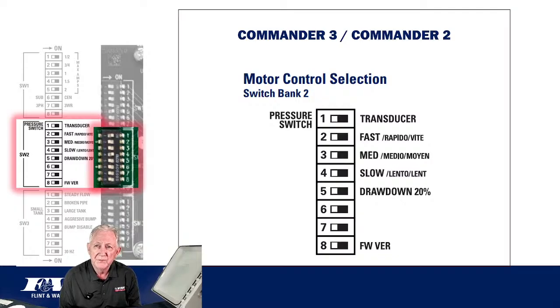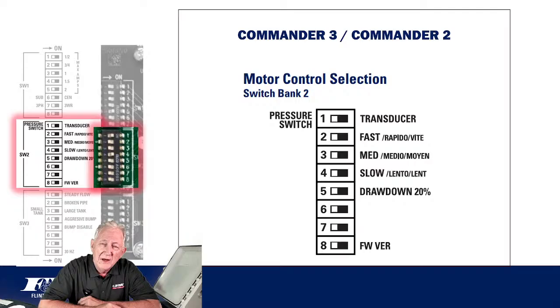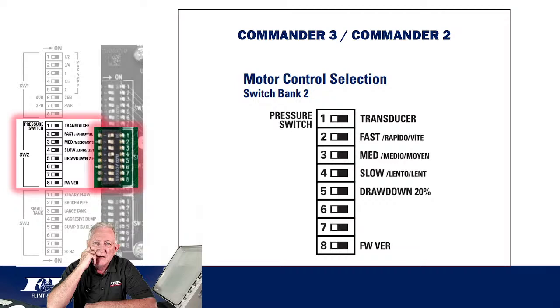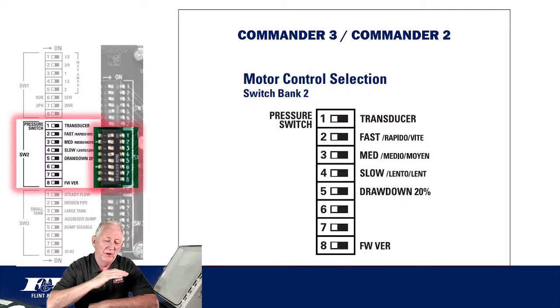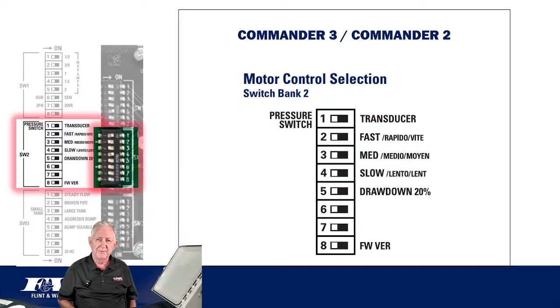Positions 2, 3, and 4 all have to do with response time. And again, not very often would these need to be changed from where they're set when it leaves the factory. But this is where we can actually increase the response time, whether it's a transducer or a switch. We can speed it up or slow it down. That drawdown, you can see that's up to 20%. That's basically how much below the pressure point we want it to drop before the drive kicks on. It's going to leave the factory at a setting of 5% below what pressure we set, but you can move it all the way up to 20%.